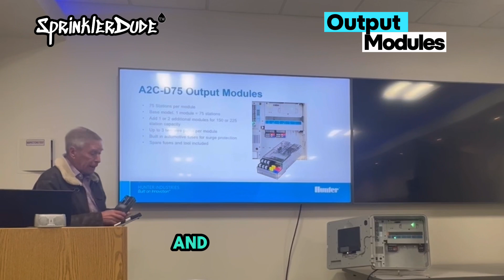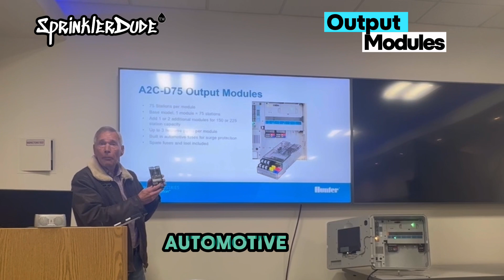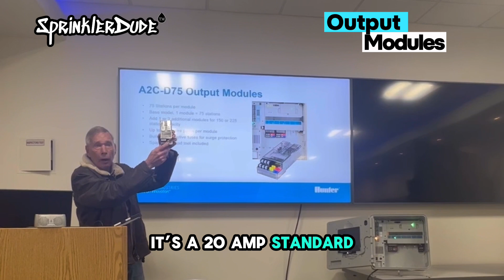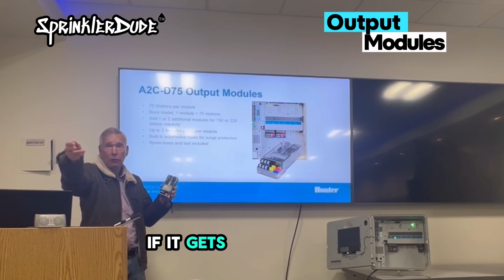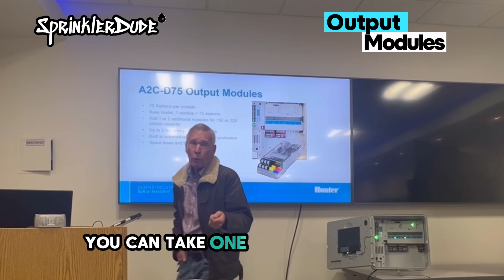And a little trick we learned from our friends in Florida, where they have a lot of lightning: automotive fuses are now on the output side of the 2-wire. It's a 20 amp standard automotive fuse. This is your last ditch attempt to stop the lightning if it gets past all your earth ground. And there's 2 spare fuses and a fuse puller tool. If you run out of all the fuses, in an emergency you can take one out of your truck. The spec is 20 amp.